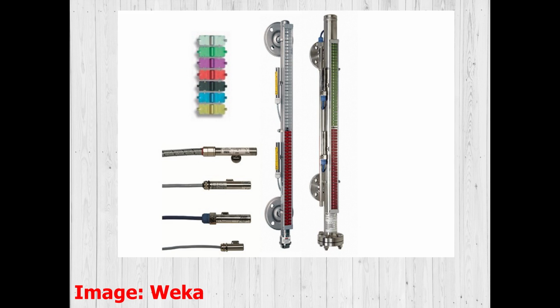A variant of magnetic connection is where the float, equipped with a magnet, is inside the tube. The magnet orients a series of magnetic tapes arranged outside and along the tube. As the level changes, the ribbons, which have different colors on their front and back, rotate and show the level of the tank.